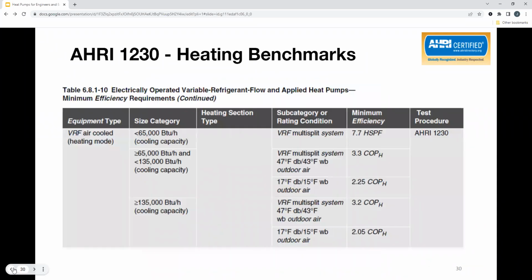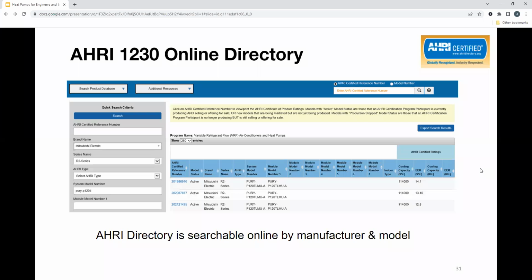And this is the heating benchmarks as well. You'll see the COPs over here for the minimum efficiencies, dependent on the size of the equipment. If you are ever looking for certain types of equipment and what the efficiencies are, you can easily visit manufacturer websites, or you can go to this AHRI directory, which is searchable by manufacturer and model. If you have a model and know the manufacturer, you can type that in, select the required fields, and pull up the nominal cooling capacities, heating capacities, and all your efficiency data.